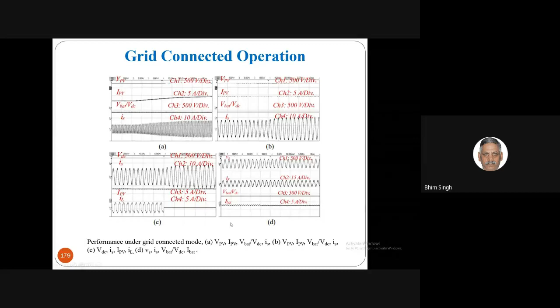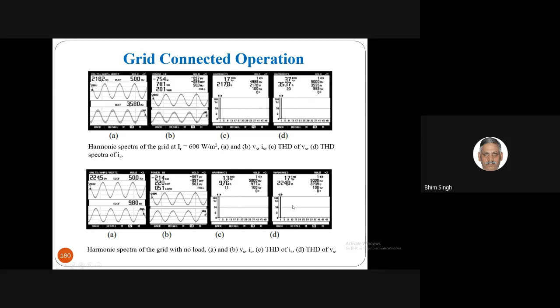And when solar insolation changes, the system works very well with no problem. When the load disappears, it still works very well, and more power is fed to the grid because the generation is fixed, and THD is always reduced to less than 5% for the current. You can see here the THD of voltage is 1.7%, but current THD is only 1.3%. It means you are filtering the voltage using the control before it is used in control also.